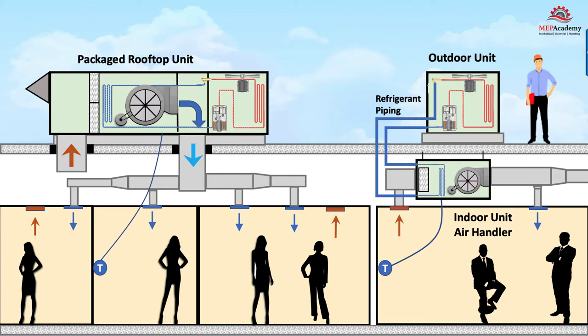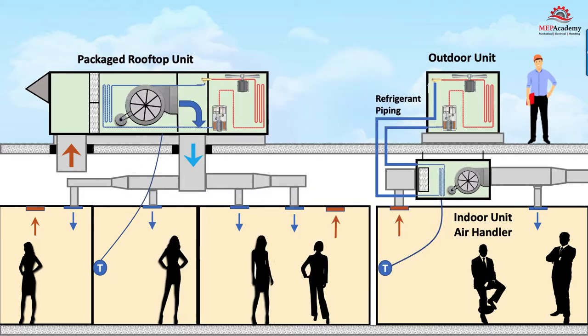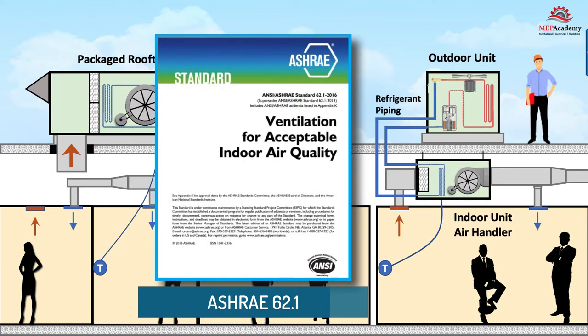Refrigerant carries more heat capacity than air, which allows small refrigerant piping to easily maneuver through building structures and components as opposed to large air ducts. This is what gives split systems their advantage, except when it comes to ASHRAE 62.1 ventilation air requirements, which we'll discuss later.